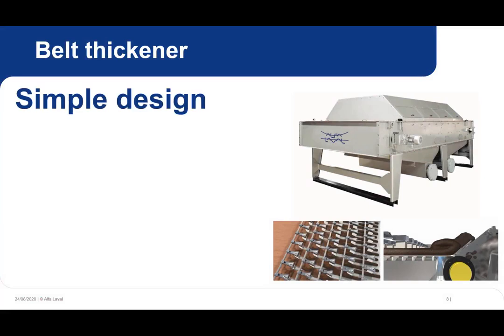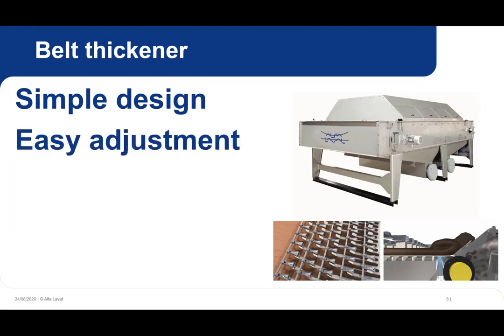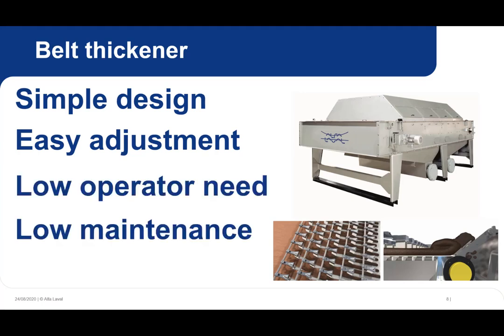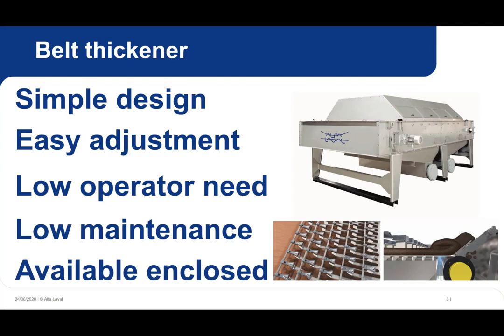A belt thickener is also a very simple design. Sludge is mixed with polymer and is distributed over a continuous porous belt. Rows of plows continuously split the sludge flow, releasing water to drain into a pan below. An adjustable ramp at the end of the belt allows easy control, and its angle will increase or decrease retention time on the belt. The belt thickener has low operator need, low maintenance, and can be enclosed for outdoor installation or to improve odor control.